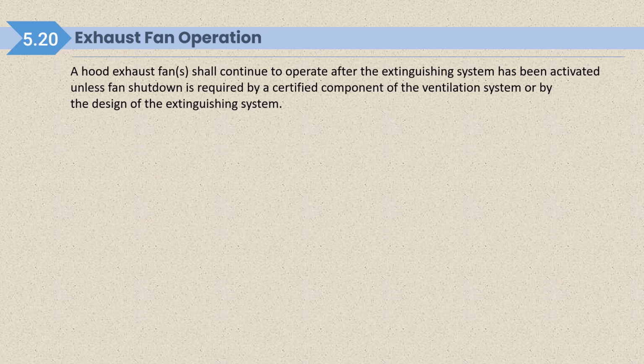Exhaust fan operation, hood exhaust fan shall continue to operate after the extinguishing system has been activated unless fan shutdown is required by a certified component of the ventilation system or by design of the extinguishing system. So we generally keep it running when fire extinguishing system activate during a fire.